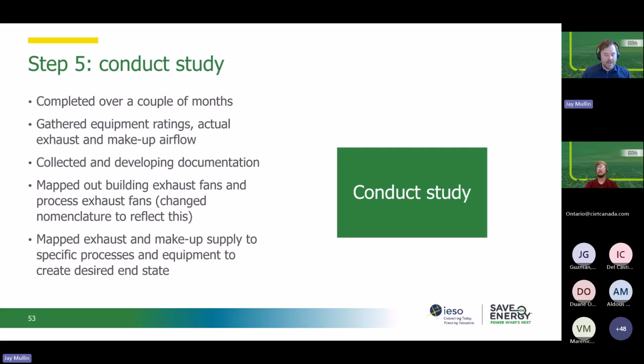But mapping out all of that exhaust, makeup, and supply, they also mapped that out tied to specific processes and equipment, to both understand the current state, but also create the desired end state. Again, with that BAS and those automated controls in mind, they wanted to be able to say, okay, if this weld booth is operational, this exhaust fan needs to be working. And if this exhaust fan is on, this makeup air unit needs to be on to counter that, or this combination of supply under different conditions. So that mapping out of the desired end state of how it would balance supply and exhaust under different conditions was a really important piece of the study and really valuable for informing the BAS operation.